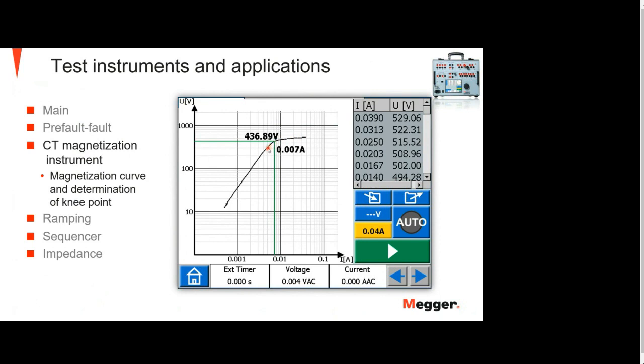So when it's going down, it will show the voltage knee point, and then automatically it will do the demagnetization completely down to 0 on the voltage. And then you're ready with the test. If you do manual, you use the knob on the Sverker 900, turn it up until the Sverker 900 screen will tell you to turn it anti-clockwise again, and then you need to push on the knob each time you would like to have the points. So when you do it manual, you need to activate by yourself, push the knob to take the test points.